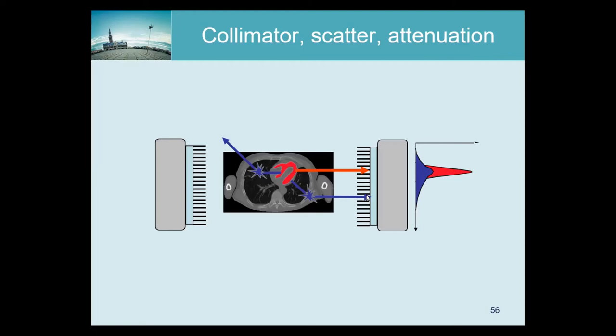And this is exactly the same effect, but now we call it Scatter because this was a photon we did not want to see. It's traveling in the wrong direction, but after scatter interaction, it travels nicely through the collimator and gets detected. As you can see, the heart which is sitting here can now contribute photons all over the place. So we get a very wide, relatively smooth contribution of the scatter. So it's dependent on the patient, but it's much smoother than the image created by the trues or the primary photons.